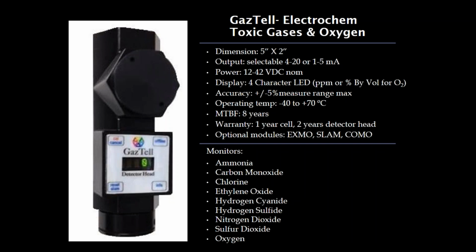Rob reminded me, we just did a couple of systems for mercaptan. In all fairness, as I told you, the mercaptans are in the sulfur group with hydrogen sulfide. So basically, you can do a lot of the different sulfides using the hydrogen sulfide cell.